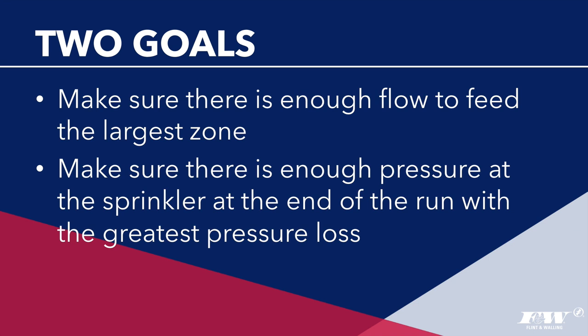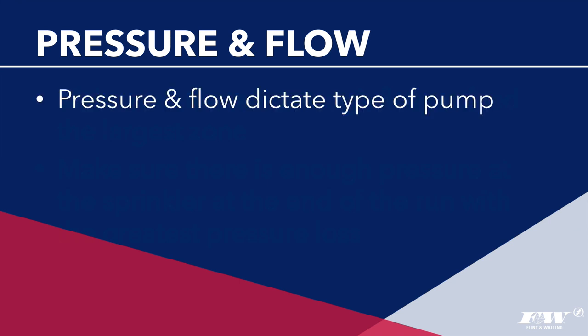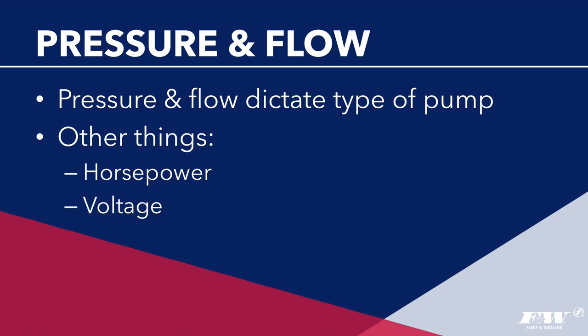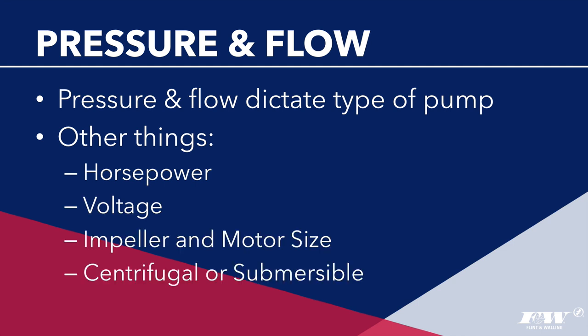If you're servicing an irrigation system, you know that if there's a problem with a sprinkler — apart from a broken or defective head — there's either not enough flow to the sprinkler head or not enough pressure to make it operate correctly. Pressure and flow are the two things that matter, and they dictate the choice of pump more than anything else. All other pump characteristics — horsepower, voltage, impeller and motor size, centrifugal or submersible — are in the service of creating enough flow for the largest zone and enough pressure to power every sprinkler head.